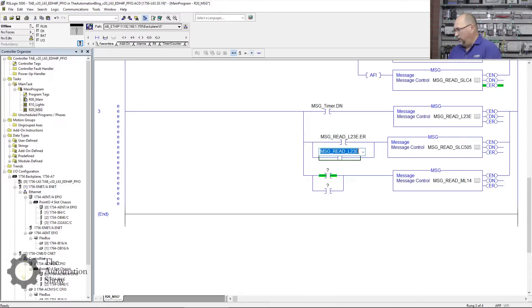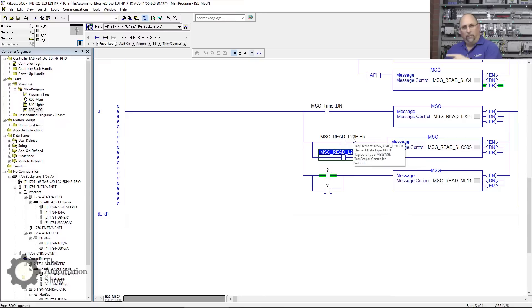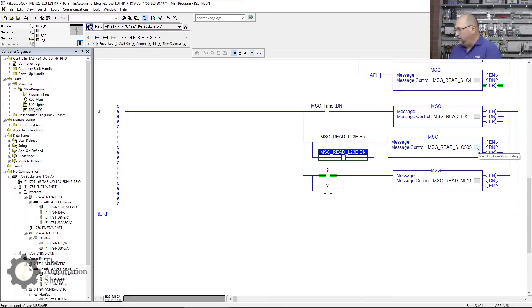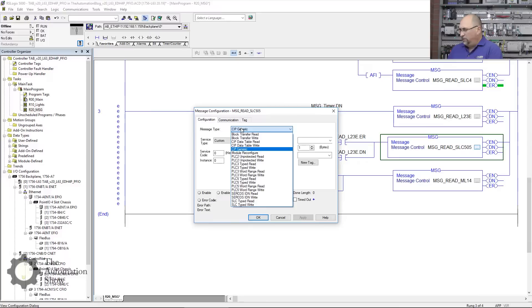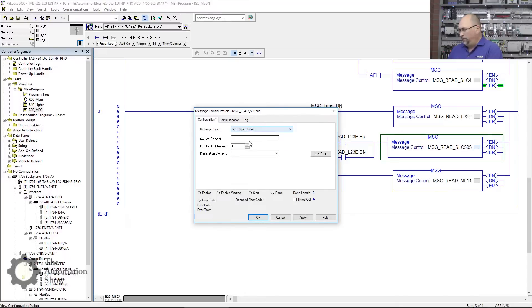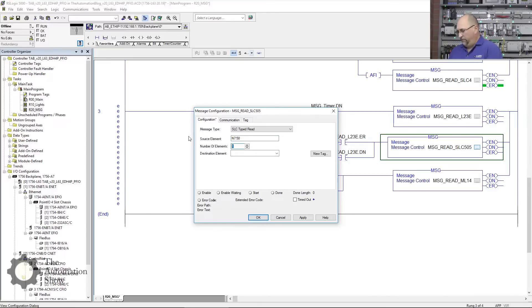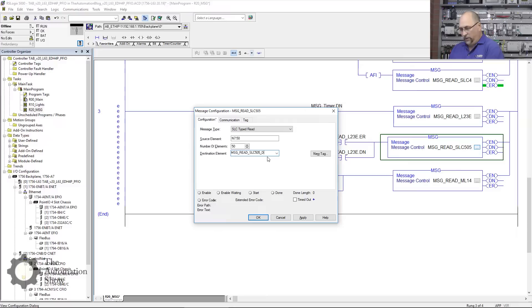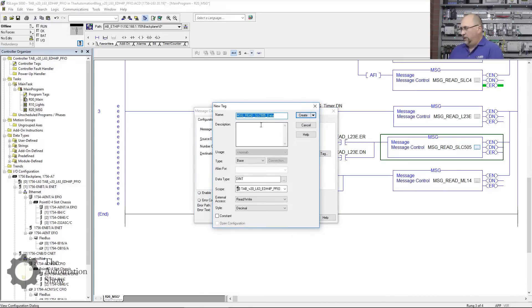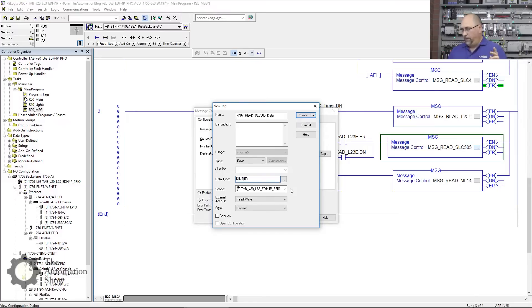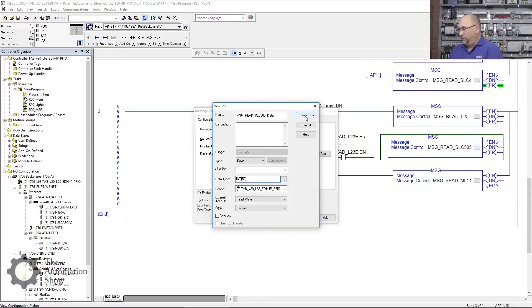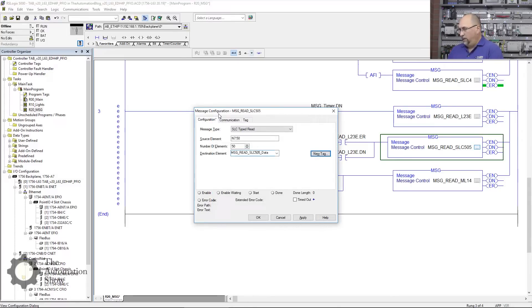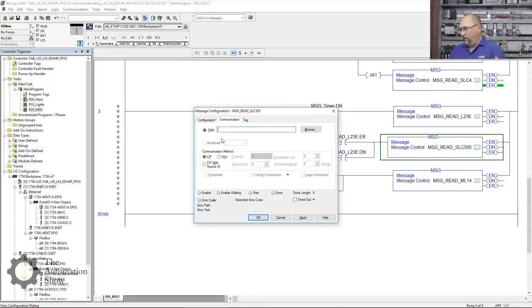Now let's do the SLC 505. We'll open that up. This is going to be an SLC Type Read. The source element—all my data for my molding machines is N7:50, and I have 50 words of data I want to read. We're going to have to create a new tag to put that into, so we'll call it MSG_Read_SLC505_Data. New tag. Now I need it to be a dimension of 50 because I have 50 words, but because it's an SLC 500, they're integers not double integers, so I'll change that to an INT[50] and create it.